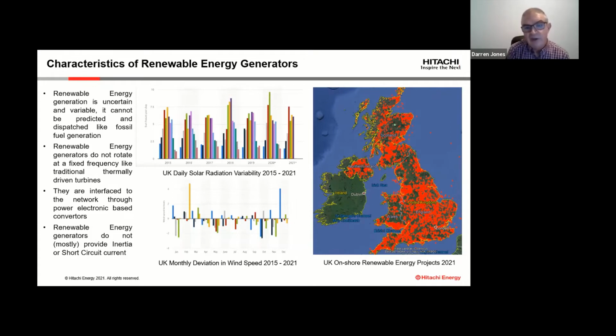The input half of the power electronic converter takes the rotation of the turbine, whatever speed that is, and converts that variable output into a DC voltage. That DC voltage then drives the output of the converter, producing a 50 hertz output that is matched and synchronized to the grid.